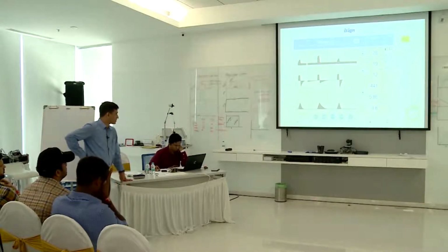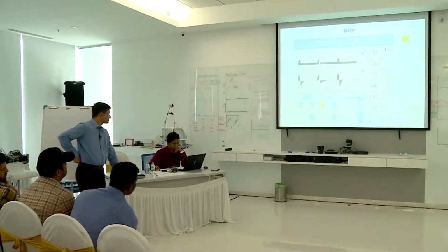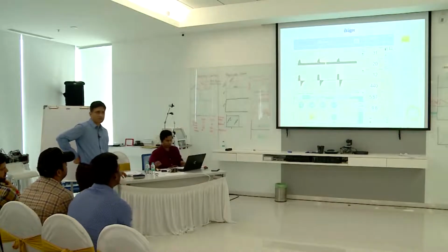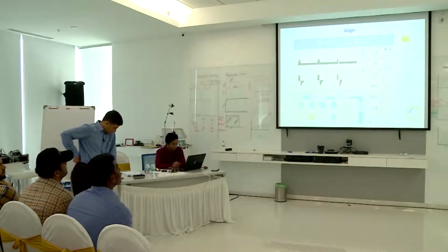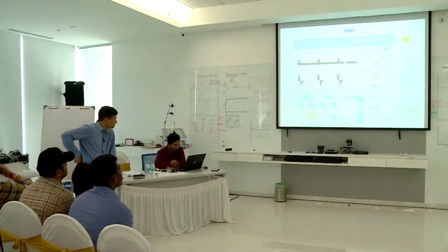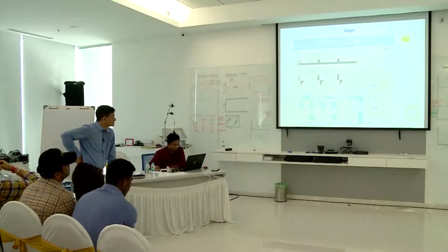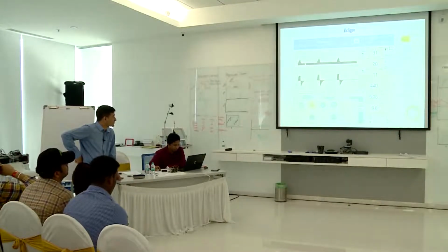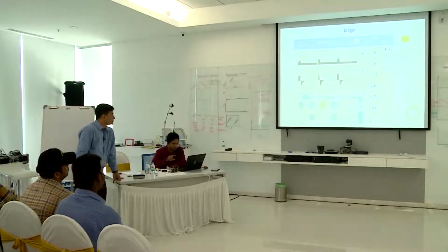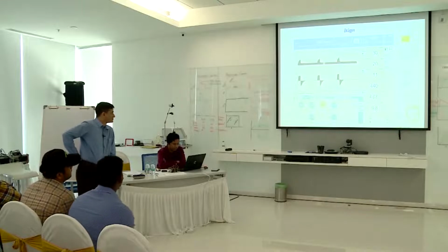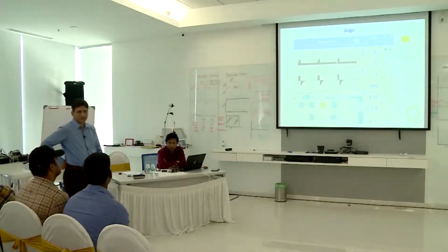So can we go down on your flow? Okay, let's see how the things change. So we have reduced the flow to 36, and now we'll check the I:E ratio. Inspiration is 1 second and expiration is 7.